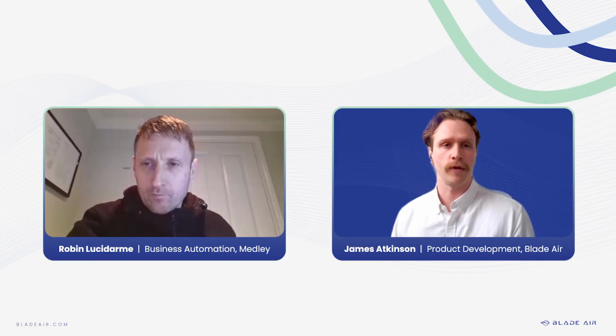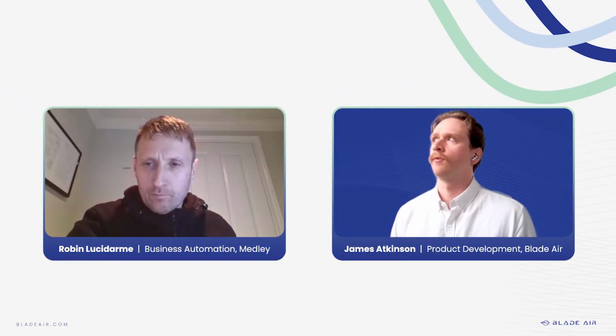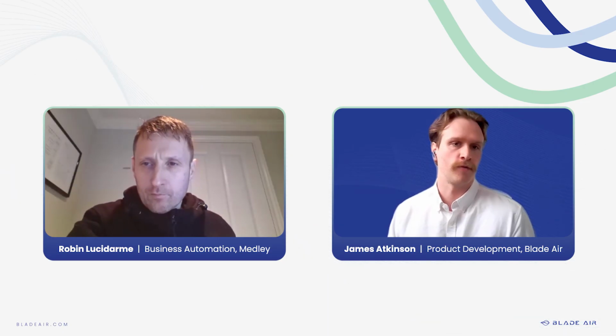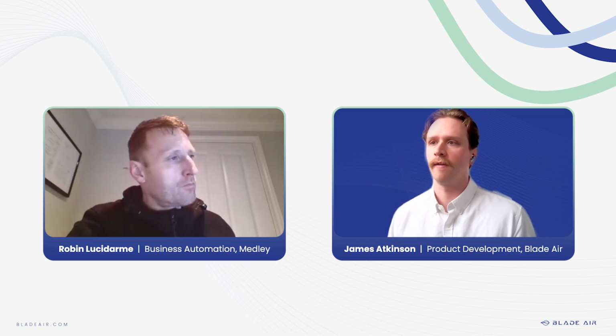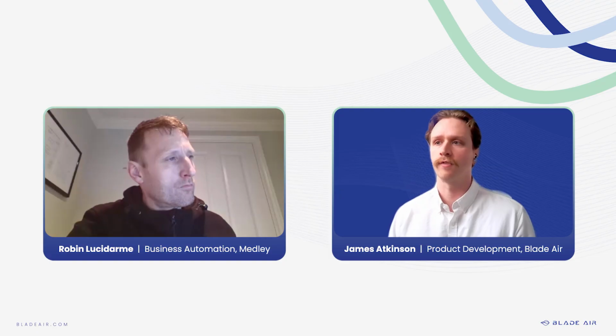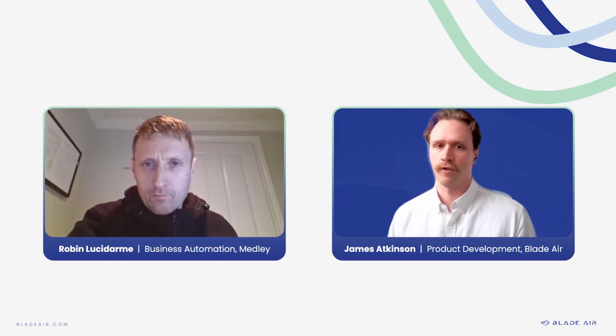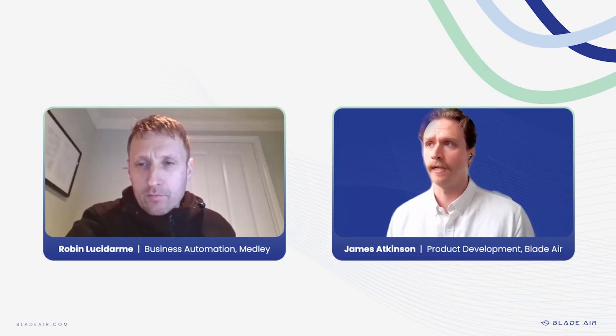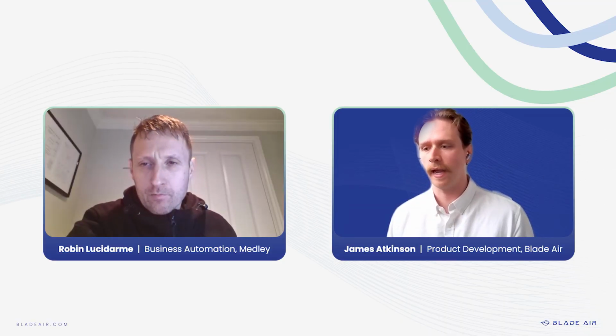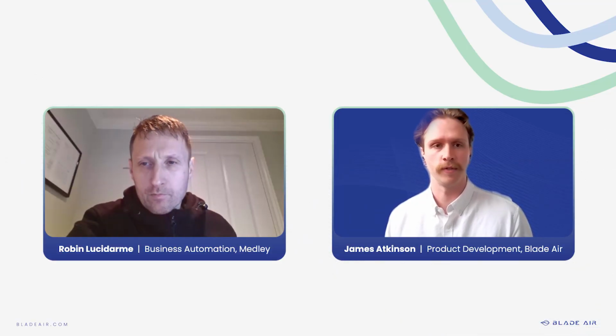So the metal frame will drop into your rack wherever you have a typical pleated filter. It's just a 1-for-1 replacement. We have had cases where people will replace a bag pre-filter and a MERV 13 final filter with just these, and they actually see better performance. Because we have that electrostatic field, this is a powered device. You're able to get much higher filtration performance with a lower pressure drop. And because of that high dust loading, you can actually combine your bag and final with just this Pro filter.